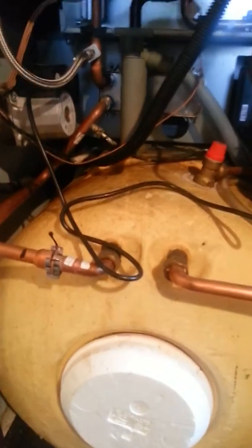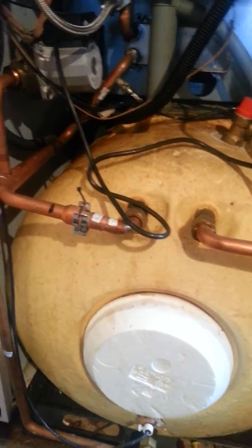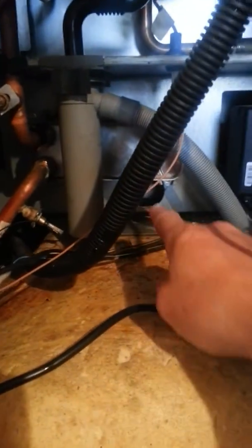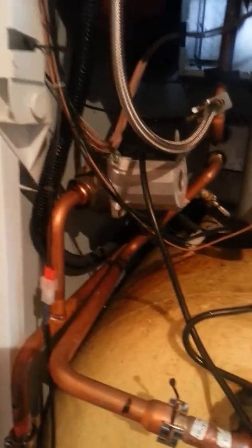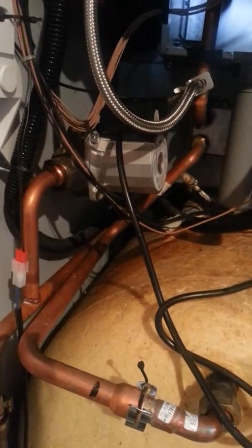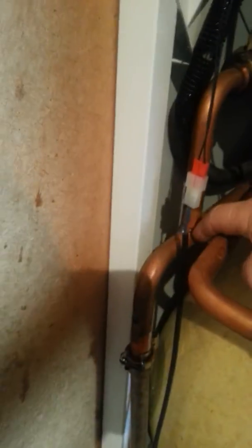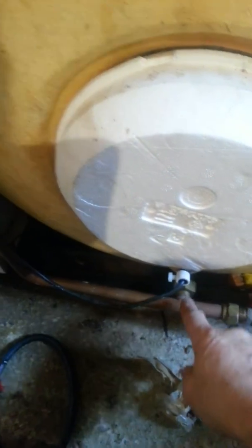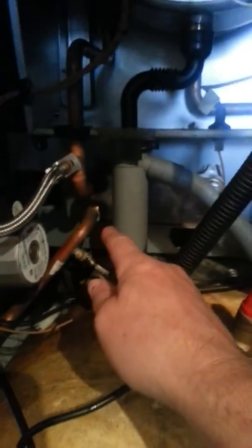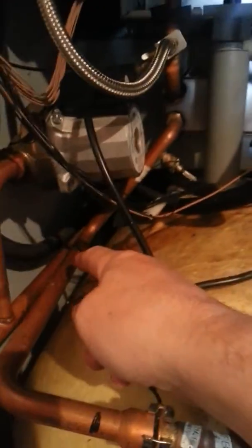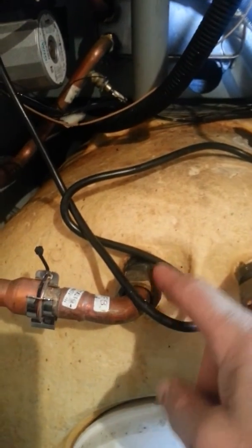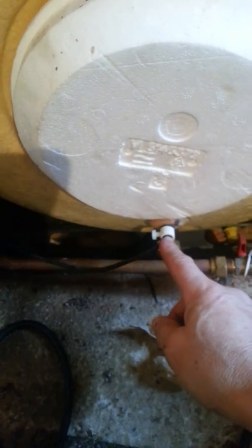Okay, so principles. Basically we've got a small cylinder in the base of the boiler and it's loaded via a plate heat exchanger at the back. So if there's no flow to the taps and the boiler needs to be loaded, we have a bronze pump here, and this draws water back from the cylinder via the cold feed in. So this is normally where the water goes in, but it reverses the flow, brings it back up, travels back up here through the bronze pump into the plate heat exchanger, back out and down into the top of the cylinder. Once it achieves temperature, this sensor at the bottom, it'll switch off.